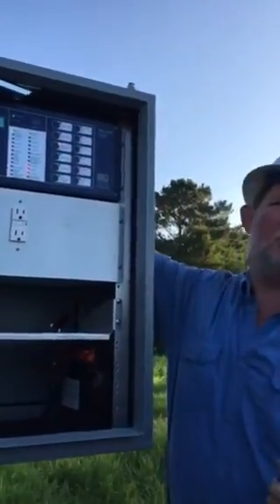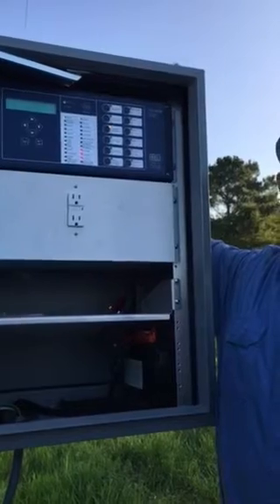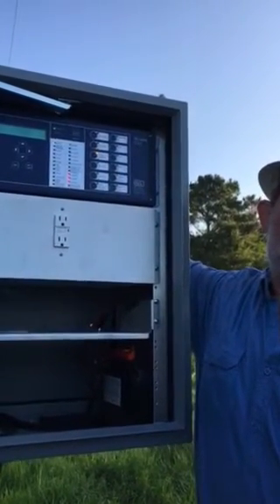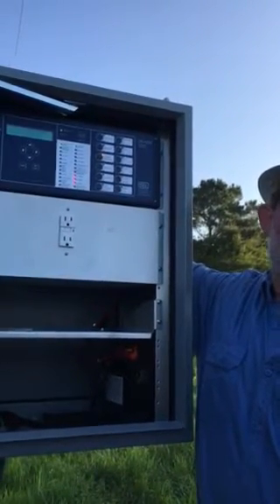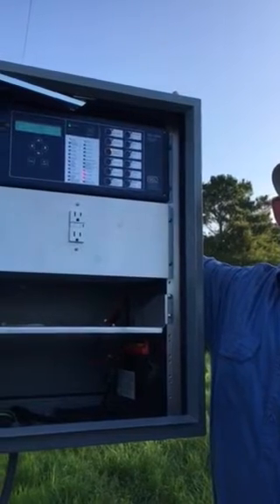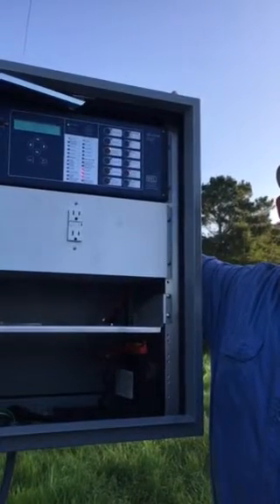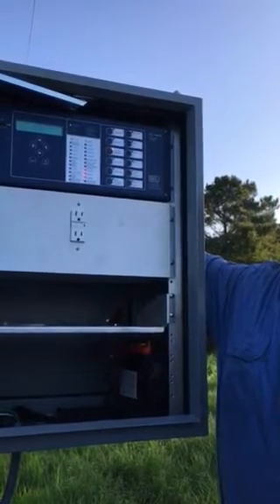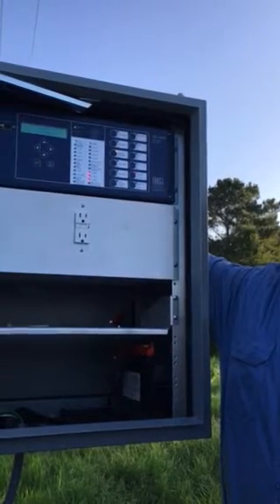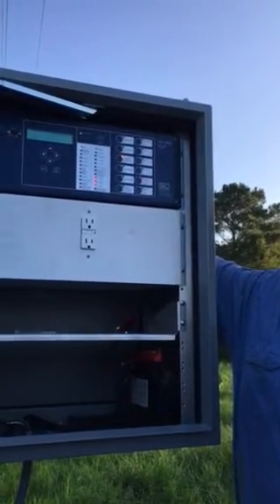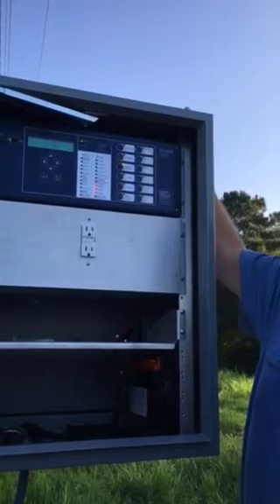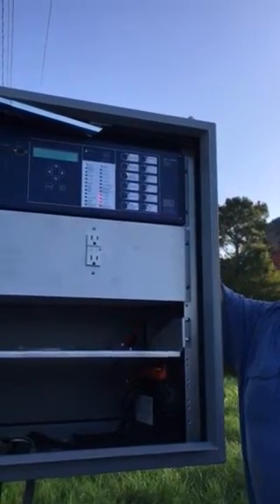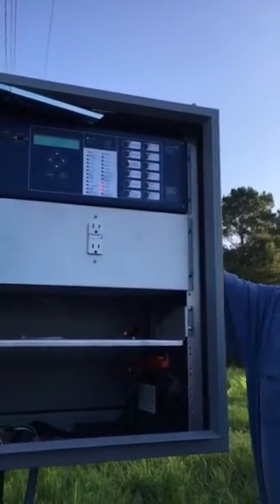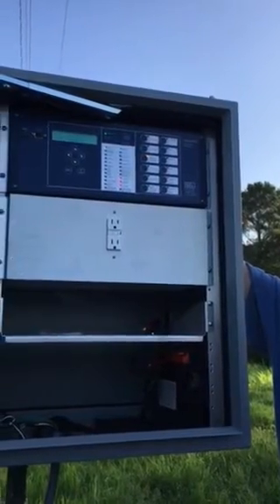What you are going to have on this circuit, though, they've already been ordered. They're getting new vacuum breakers. It's a different company. It's not going to be Siemens. It's Schrader. We're getting all new vacuum breakers for Poplar Street. They're going to have the 351s in them, so they will tell you which phase. It won't tell you the high amp reading on what phase if you scroll through? No, not right now. They may set it up to do that. Right now, the way they got it set up, you're reading the amps coming off the solar field.